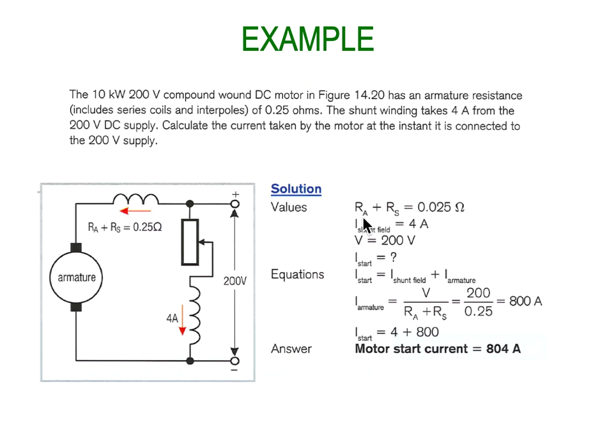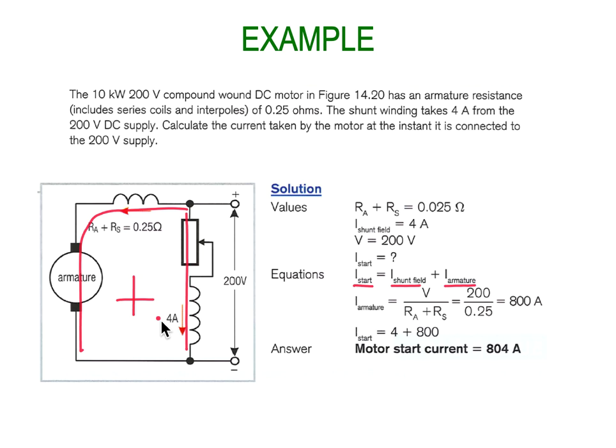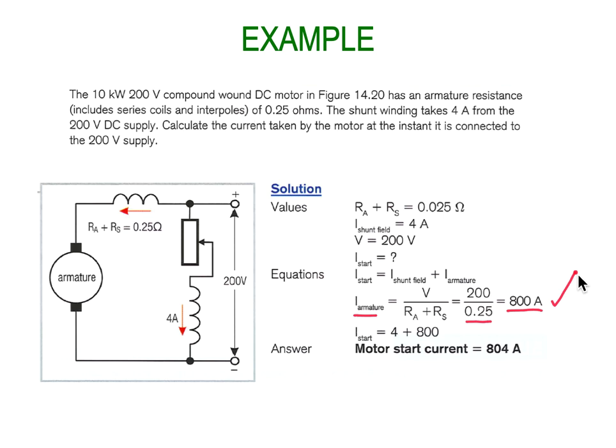The shunt winding takes 4 amps at 200 volts DC. We're going to calculate the current taken by the motor at the instant it is connected to the supply. We take the resistance of the armature, 0.25 ohms, and we know the shunt field is pulling 4 amps at 200 volts. The armature current is simply the voltage divided by the resistance: 200 divided by 0.25 is 800 amps.